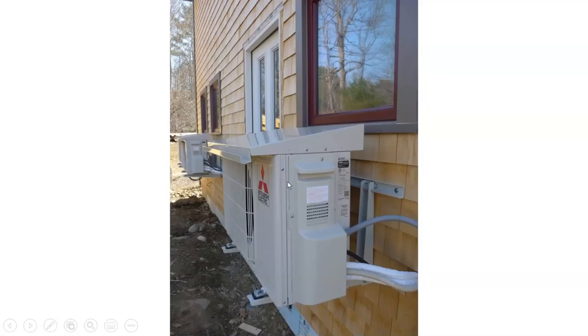This is a picture of a mini split condenser with a hat on it to shed water, to make sure water doesn't settle on top of the condenser during rain or snow, and freeze and restrict the flow of air through the condenser. We require these in all the installations also.